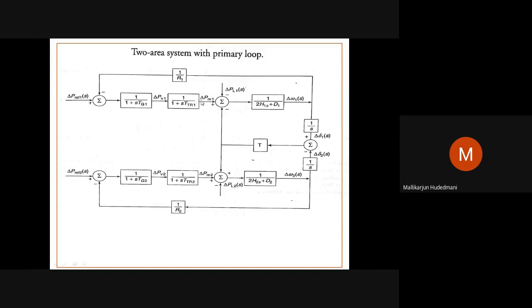This mechanical output, which is connected to the shaft of the generator, again makes the generation adequate to the change in mechanical power, such that there was a need as the electrical load was increased. Why does frequency deviation occur? Maybe there was a load insensitive to the frequency, infinitesimally small, or there was a frequency-sensitive load over there with a D. What has really caused it has to be addressed by the area and this control. So that has been seen in the primary part of the ALFC in a single area.